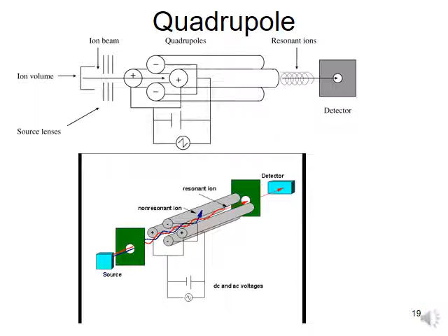The ions passing through the ionizer go here as the ion beam, and then pass through the quadrupole. After passing through the quadrupole, the ion molecules with different masses will be separated according to the mass. Here you can see the resonant ions. After that they pass through the detector. So this is the concept: from the source, to the quadrupole, and then directly to the detector. This quadrupole needs a current as an energy supply. Basically this is the explanation of the quadrupole.